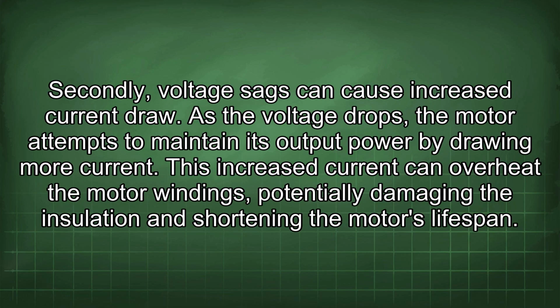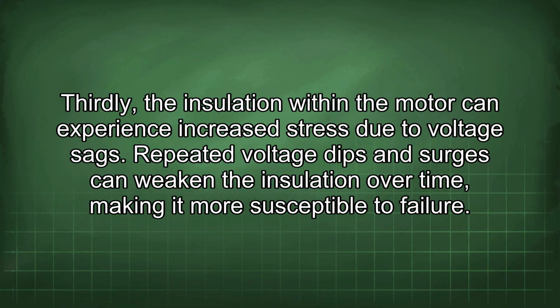Secondly, voltage sags can cause increased current draw. As the voltage drops, the motor attempts to maintain its output power by drawing more current. This increased current can overheat the motor windings, potentially damaging the insulation and shortening the motor's lifespan. Thirdly, the insulation within the motor can experience increased stress due to voltage sags. Repeated voltage dips and surges can weaken the insulation over time, making it more susceptible to failure.